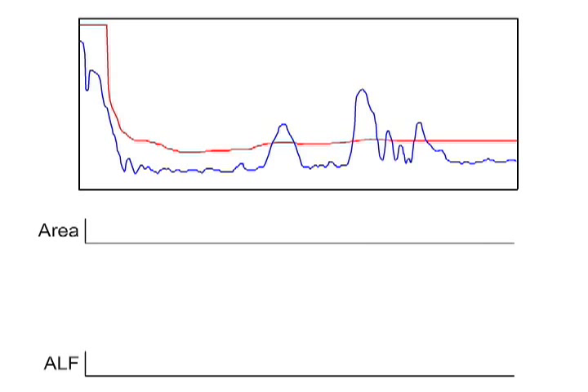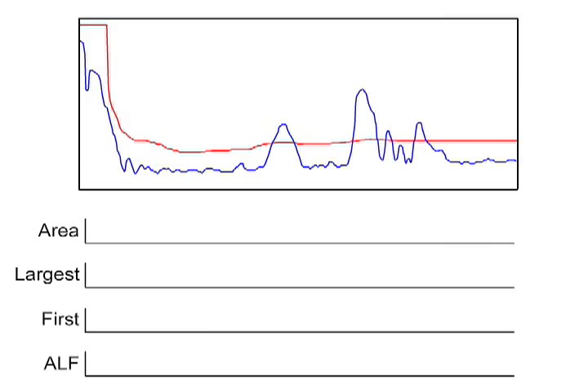ALF stands for area, largest, and first. The ALF algorithm will evaluate all of the echoes above the TVT curve and give them a score based on the amount of area under the curve, the height of the echo above the TVT, and the echo's position along the TVT curve.